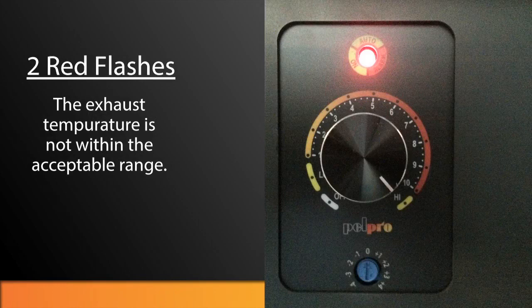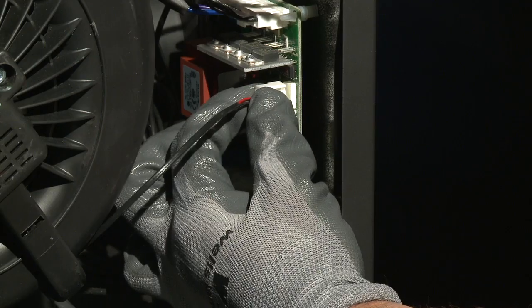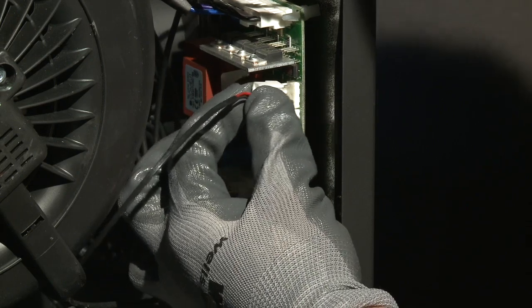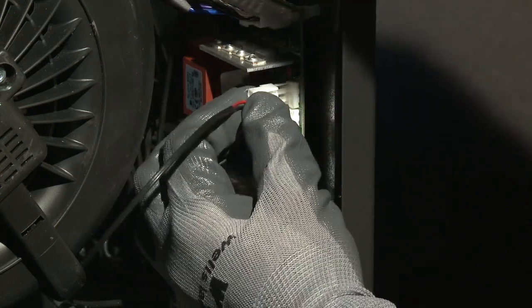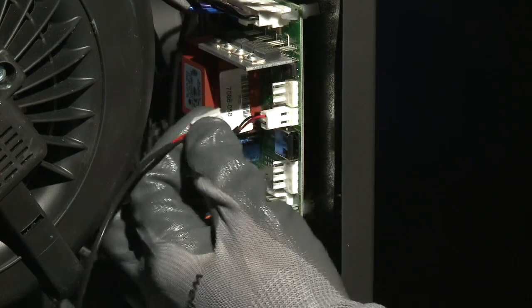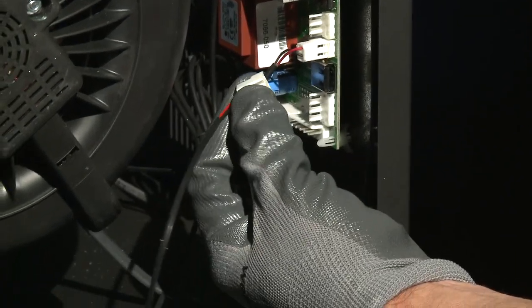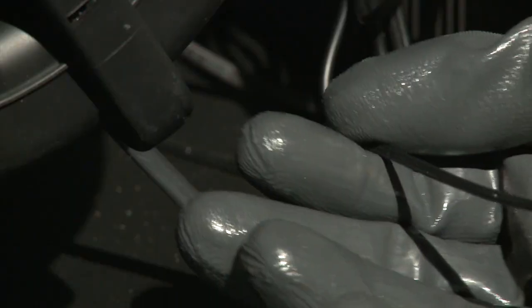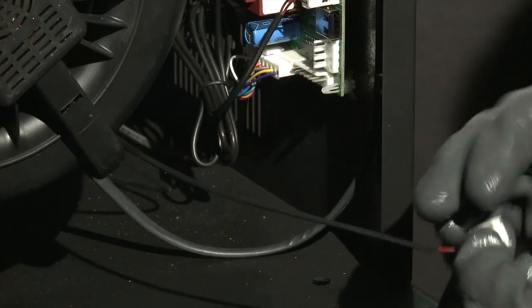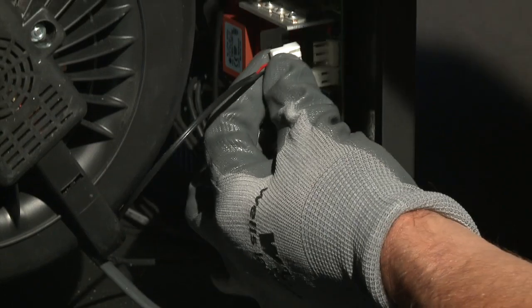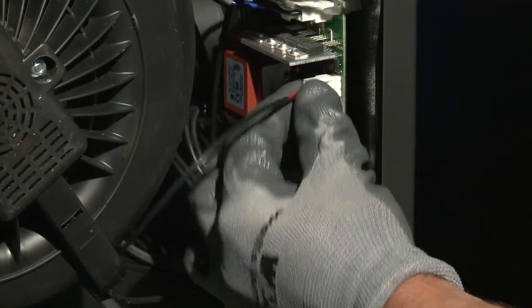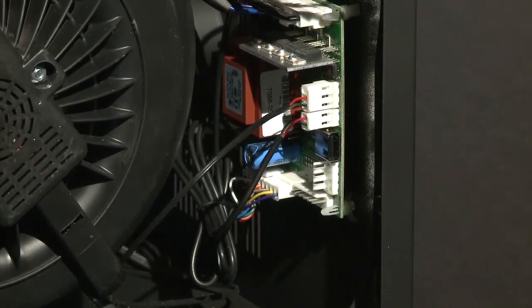2 red flashes means the exhaust temperature isn't within the acceptable range. This could mean that the exhaust temperature probe has been disconnected from the board. Simply plug the probe back into the board. If this doesn't work, unplug the probe, inspect the connection, and check the entire wire for damage. Plug the probe back in. If you see 2 red flashes on the control, replace the exhaust temperature probe with a new one.